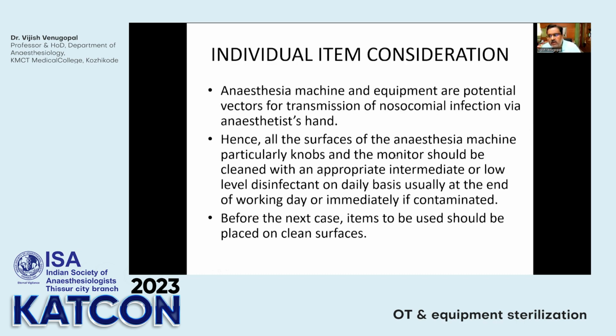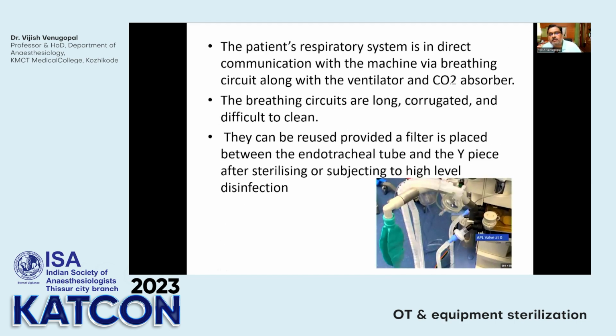Now coming to individual item considerations, the anesthesia machine and equipment are potential vectors for transmission of nosocomial infection via the anesthesia person's hand. So we should make sure that before the next case, the items that are kept should always be on clean surfaces. Now, the patient's respiratory system is in direct communication with the machine via the breathing circuit. These are very long, corrugated, and difficult to clean. And if you are going to ETO sterilize them, make sure that there are no water particles. So it should be air dried before you ETO them.